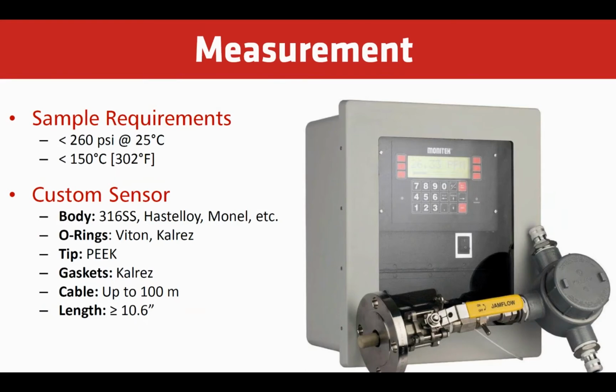The O-rings that seal the gland and the sensor tip, standard is Viton, but for some nastier samples that would attack Viton, we offer up to Kalrez. The sample tip is made out of PEEK. The gasket between the PEEK tip and the metal probe shaft is always Kalrez, and we offer cables up to 100 meters in length. The standard probe length is approximately 10.5 inches long, and that is also custom built depending on application and sizing of your pipes or the riser coming off of your pipe.